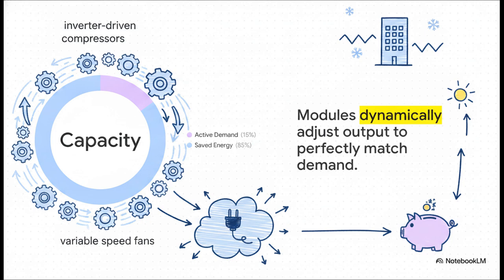But today, the tech has finally caught up. Thanks to inverter-driven compressors and variable-speed fans, each individual module dynamically adjusts its output based on what the building actually needs right then and there. A module can scale its active output anywhere from 15 to 100% capacity. That big chunk of saved energy goes straight back to the bottom line. Whether occupancy fluctuates or the seasons change, the system matches the load exactly.